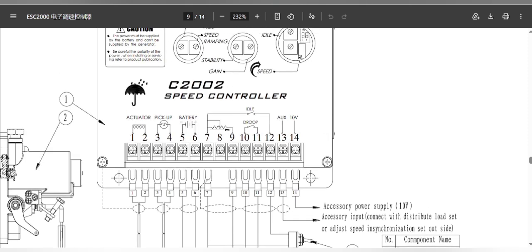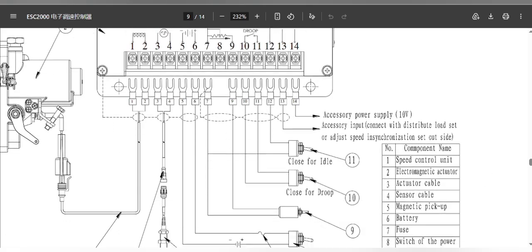Understand? Idle speed means if you are operating the generator at 1800 rpm, you should be able to set 800 rpm for idle. Idle means the engine is running at a very low speed, about half of the rated RPM. When the engine is well lubricated, warmed up and ready for operation, idle should be only 1 or 2 minutes, not too much. You cannot run the engine idle too long. Then the engine should leave idle and reach the rated RPM, 1800 or 1500 RPM.